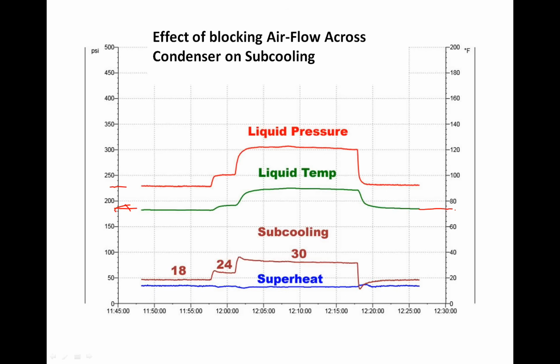We're somewhere around 80 degrees liquid temp, 70, what is that, 65, 70, 75, 77 degrees or so of liquid temperature, and that resulted in a subcooling somewhere around 18 degrees, right? These are temperatures on the right, and these are pressures on the left. So somewhere around 18 degrees. When I block that condenser off, right, I increase the head pressure up to 250, you can see it resulted in a corresponding increase in subcooling. And then I blocked it off again, and it also increased the subcooling again.